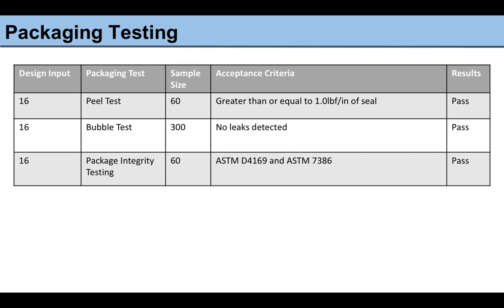We also tested a bubble test to confirm that the packaging had no defects or weak spots, and this was to ensure the safety of the packaging. This had a sample size of 300 because it was an attribute test, and the acceptance criteria of this test was no leaks detected, which passed. Finally, we tested the package integrity with a sample size of 60 because it is variable data, and the acceptance criteria is outlined in ASTM D4169 and 7386, and this is a standardized packaging test, which passed.